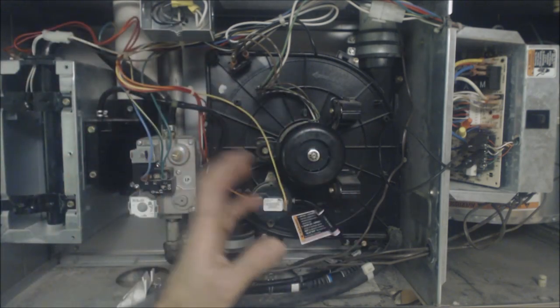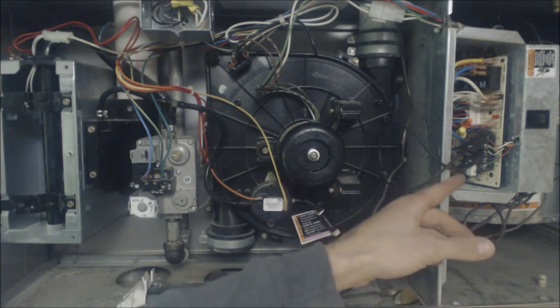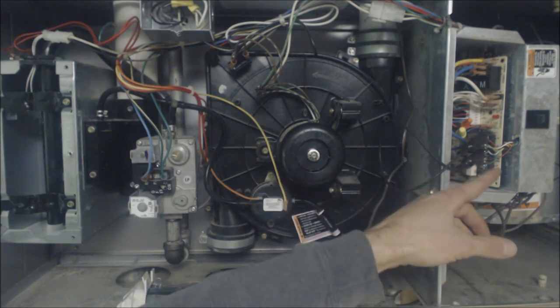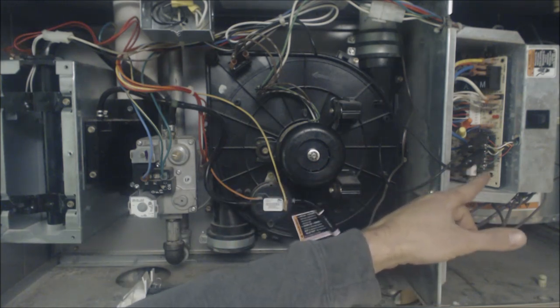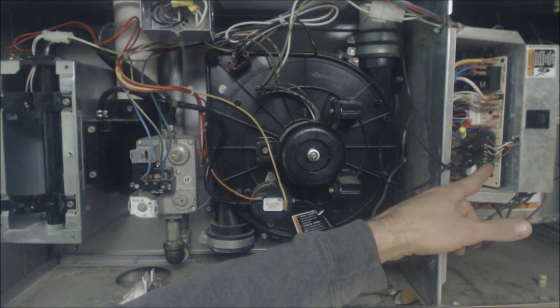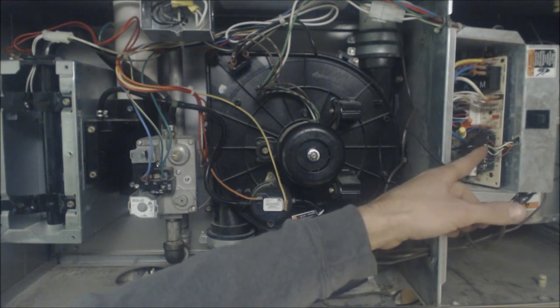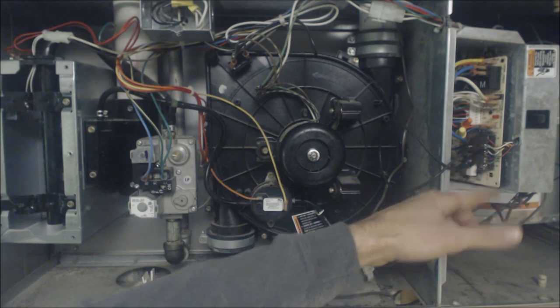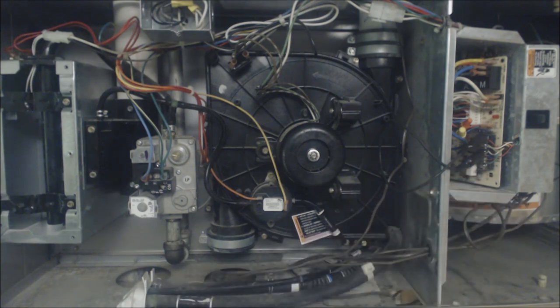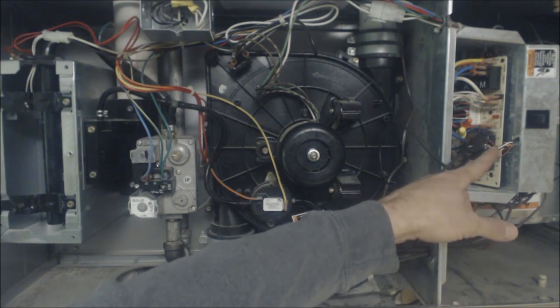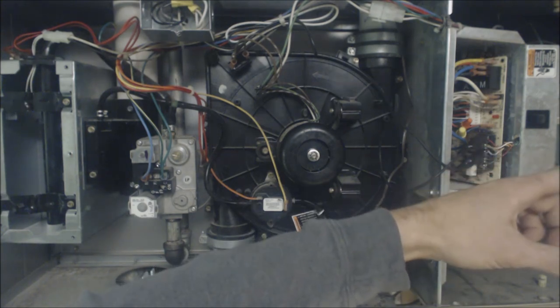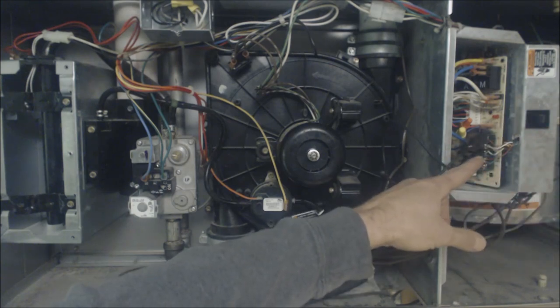If you were to turn heat on, which means that you're going to have 24 volts from W to C, okay, because you have a jumper from R to W. Alright, so 24 volts is on R, it goes to the thermostat and it comes back to the W as 24 volts.